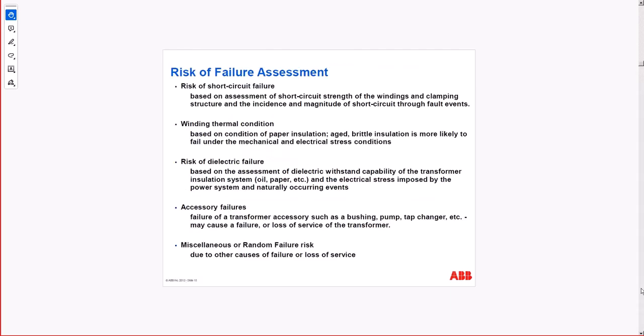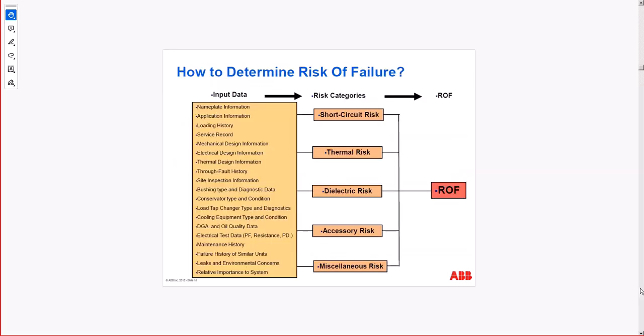Risk of failure: short circuit, winding conditions, risk of dielectric failure, accessory failure, and random failure. And here is a map of the failures. Risk of failures can come from all this. Pretty much you have here 5 categories that are listed: the short, the thermal risk, the dielectric breakdown, accessory risk, which includes the tap changers, and then miscellaneous risk from other elements like the motor of the tap changers and so on. Any questions?